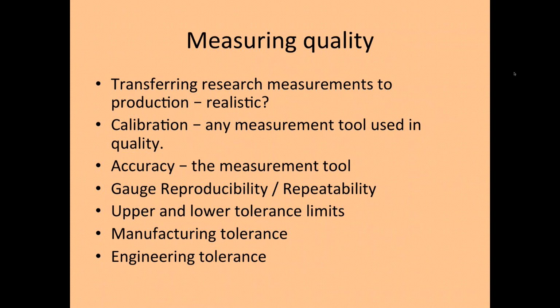This looks at the error introduced into your production or engineering tolerances and acceptable tolerances. So if your tolerance is plus or minus 0.03 of an inch, but your gauge is only good to plus or minus 0.05, you can see that your gauge can introduce so much error into your measuring that you'll be accepting product that should be rejected. So you set realistic upper and lower tolerance limits.